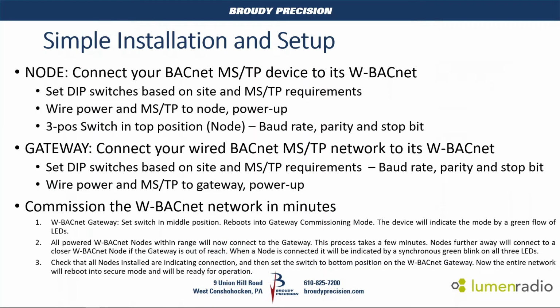With the installation and setup, basically you wire the devices up, set the dip switches, and on the nodes, make sure that that 3-position switch is set to the up position. And you would then, once everything's powered up, you would take the gateway device and make sure again it has its dip switches set up, power it up, and then first step is set the gateway switch to the middle position. It's going to reboot into the commissioning mode, and the device will indicate that it's in this mode with a flow of the green LED indication. The 3 LEDs, it'll just circle through top, middle, bottom, indicating that it's in a commissioning mode.